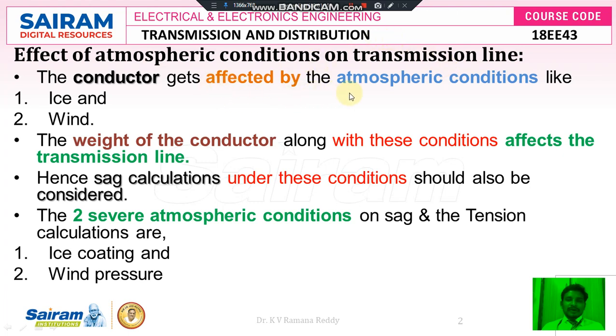The conductor gets affected by atmospheric conditions like ice and wind. The weight of the conductor along with these conditions also affects the transmission line, because during winter season due to snowfall, snow forms as an outer surface layer on the bundle conductor, increasing the overall weight. Hence sag calculations under these conditions must also consider the weight or effect of ice on the conductor. The two severe atmospheric conditions affecting sag and tension of overhead transmission line calculations are ice coating and wind pressure.